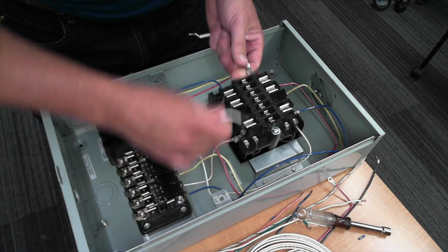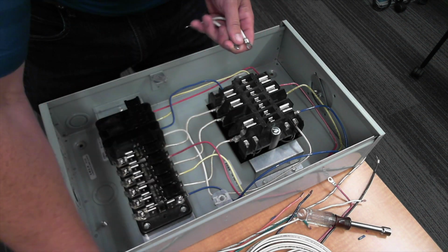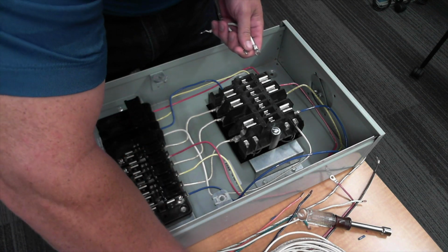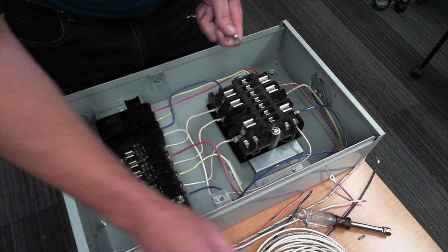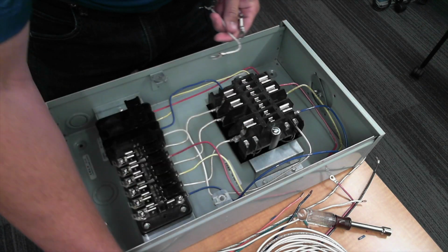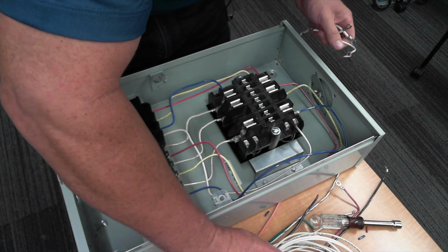This is where Jeremiah is going to tie the returns together on the CTs. That's why, when you get ready to do your measurements or a burden measurement or anything, as long as all of those returns are tied together on those CTs, you just need to connect onto one of them and you'll get the return back.